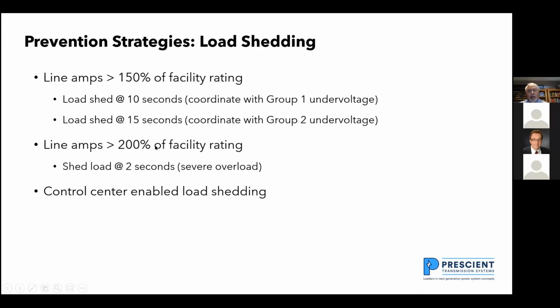If I get a facility loaded to 200% of rating, 200% of rating is a severe overload. That's going to cause the conductors to heat up and possibly sag down into something. So I should start shedding load at 2 seconds. And when I'm looking at load shedding like this, I'm looking at control center enabled load shedding, because I'm not looking at tripping the facility that's got the overload. I'm looking at tripping neighborhood substations. So if I trip loads in neighborhoods, I'd reduce the impact on the power grid and reduce the possibility of a wide area blackout.